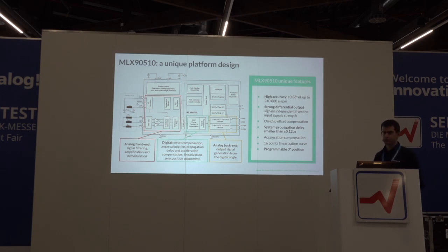The tracking loop also includes a linearization feature, so you can actually program a 16-point linearization curve that can be used to counteract inaccuracies of the sensor coming from coil non-idealities or from mechanical tolerances.